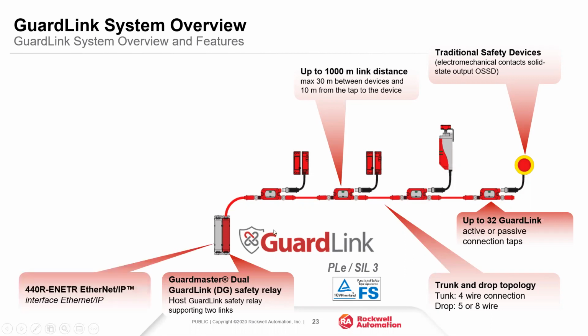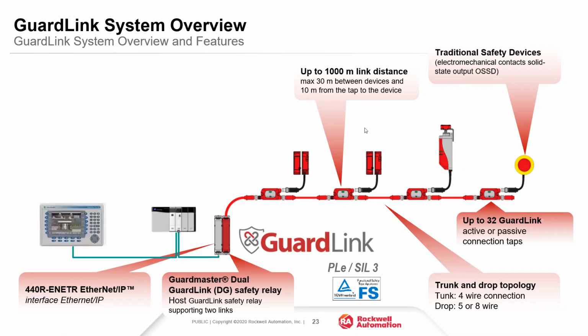And then what brings us back into the connected enterprise is there's an Ethernet IP interface module that sits next to the GuardLink safety relay. It talks optically, and that allows the information coming from the DG safety relay to be pulled back into the controller and the HMI. And again, that provides the diagnostics. You can then request lock or unlock for your guard locking applications over the network. You can do resets and things like that over the Ethernet network back to the GuardLink safety monitoring relay.